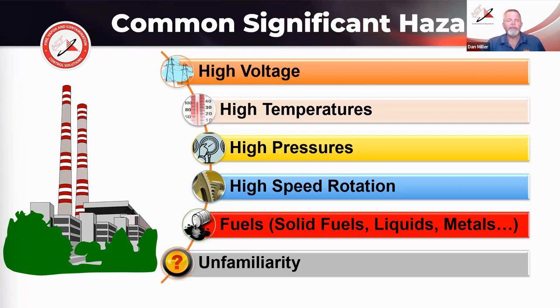And then the many different kinds of fuels involved in the power industry. We have solid fuels in the form of coal and so forth, liquids, combustible metals, combustible dusts. Those dusts can accumulate and begin to combust while in a silo, for example, as the coal degrades, gets wet or too dry, or in piles and so forth. That combustible dust can then turn into a combustible dust explosion if we don't mitigate or manage it correctly.